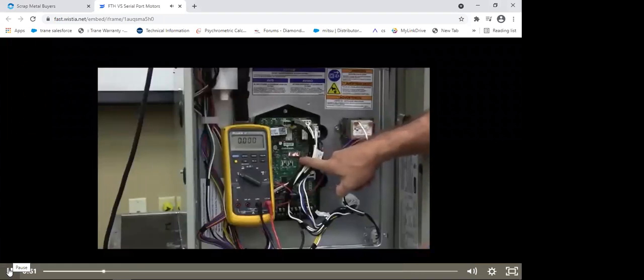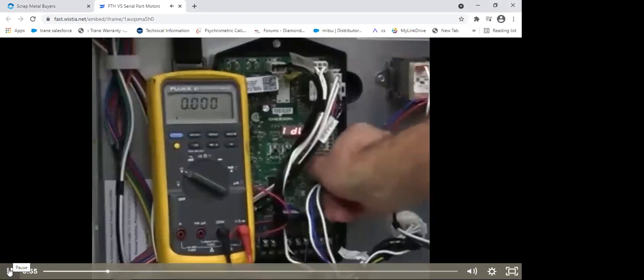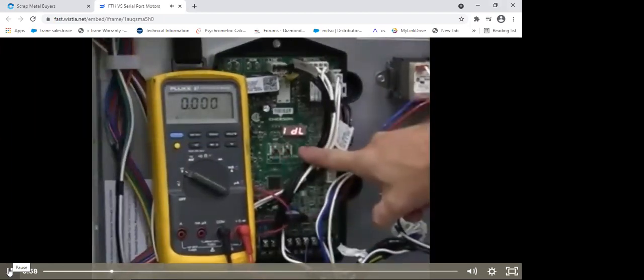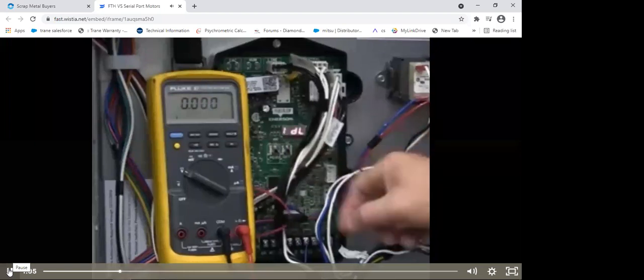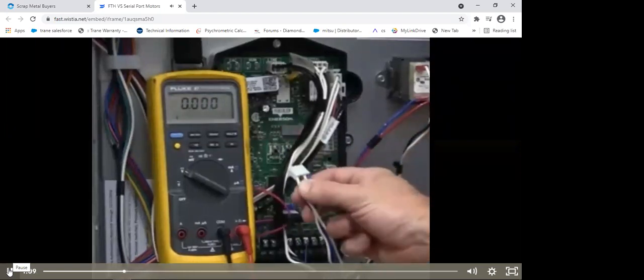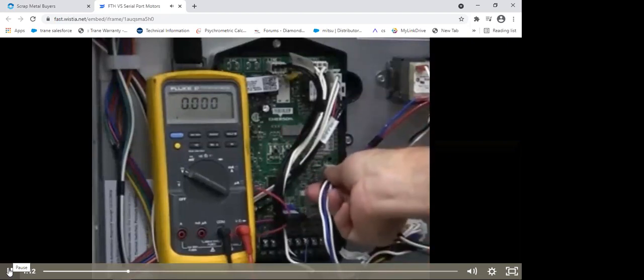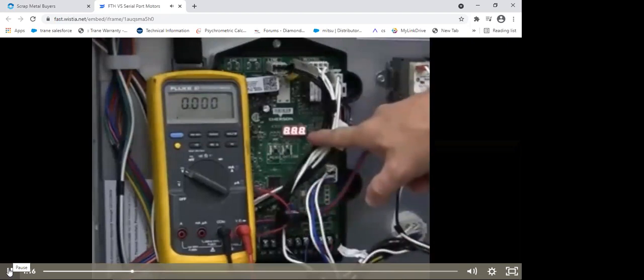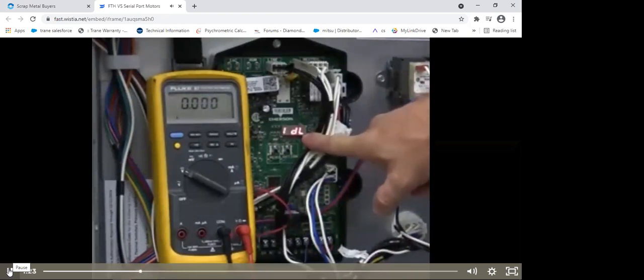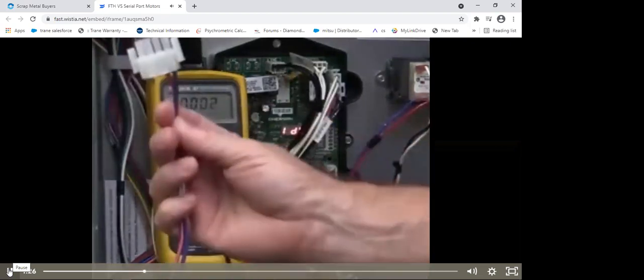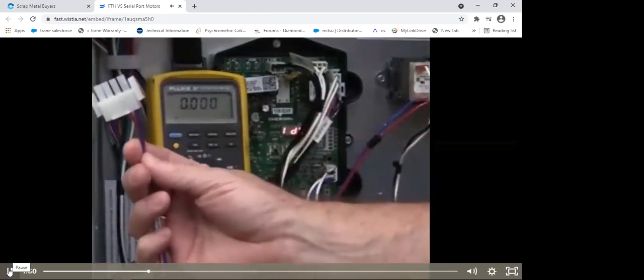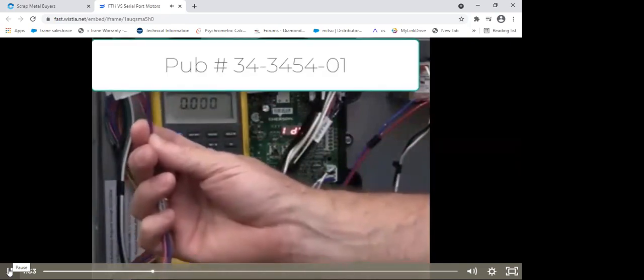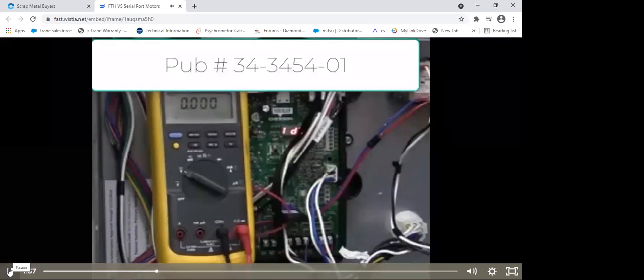The motor does communicate with the control board. So you can see right now the furnace is idle, but as soon as I disconnect my communication from the motor and the board, I'm going to get an E17 for an alert. And that tells me I have a blower communication error, in which case I'm going to be looking at my connections. Here it's obvious I disconnected it. It may be a loose connector within the pin, or it may be a broken wire between the motor and the control board. Once I reconnect, it'll recognize the motor communication and go back to the normal idle mode. And this is true of the 7-segment on the air handler and also the IFC on the furnace. Now the connector that I showed in the example can be ordered. That is publication 34-3454-01. And this harness can be ordered through ComfortSite and DealerNet under the Marketing Center and order marketing materials.